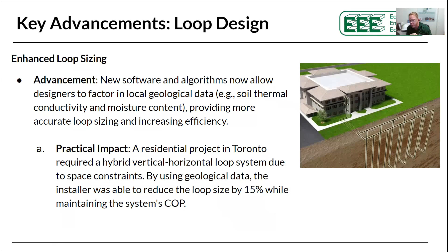In some cases it can make a big difference. If you start looking at hybrid systems like vertical-horizontal loop system designs, you can actually increase the overall COP of that unit just by using software and being involved in the design phase, taking advantage of new technology. Just because you have a lot of experience and have done a lot of ground loops and understand your market doesn't mean there isn't an opportunity to use new software and enhance your knowledge. I know I certainly do as part of my role. Using new software makes a big difference.